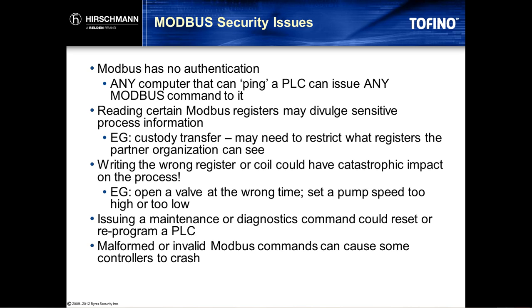Because Modbus is a very old protocol, there are some security issues involved with it. First of all, the protocol itself was designed in an era when security was just not a concern for automation systems. As a result, when we use Modbus protocol over a network, there is no way for the Modbus slave device to authenticate that the master that's sending commands to it actually has the authority to do so. Essentially, if you can ping a Modbus slave, you own it. You can send any Modbus command to it that not only reads data from the device, but also writes and makes changes to the device. So clearly, sending the wrong command at the wrong time could have a disastrous effect on the plant that's being controlled.